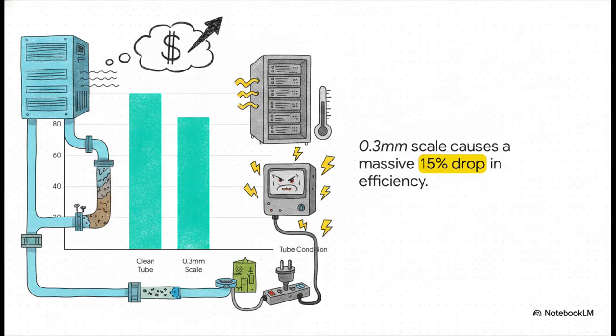To put that into perspective, that barely there 0.3 millimeter layer absolutely destroys the chiller's heat exchange efficiency, dropping it by a massive 10 to 15%. And when efficiency drops, the chiller's compressors have to basically go into overdrive just to compensate. They become massively overloaded, sucking up vastly more electricity. For a data center running 24/7, 365 days a year, a 10 to 15% efficiency drop means power bills skyrocketing by hundreds of thousands of dollars. It's a massive hit to the facility's bottom line.